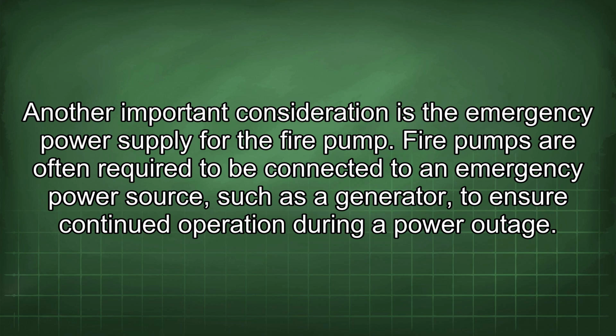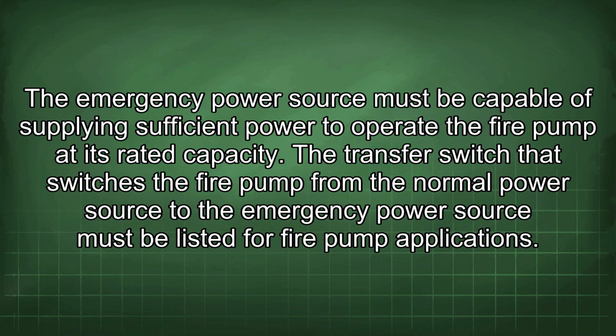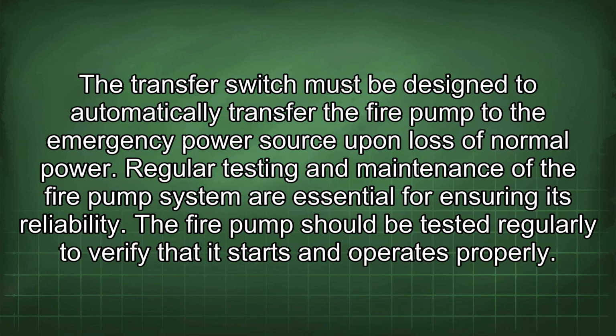Fire pumps are often required to be connected to an emergency power source, such as a generator, to ensure continued operation during a power outage. The emergency power source must be capable of supplying sufficient power to operate the fire pump at its rated capacity. The transfer switch that switches the fire pump from the normal power source to the emergency power source must be listed for fire pump applications. The transfer switch must be designed to automatically transfer the fire pump to the emergency power source upon loss of normal power.